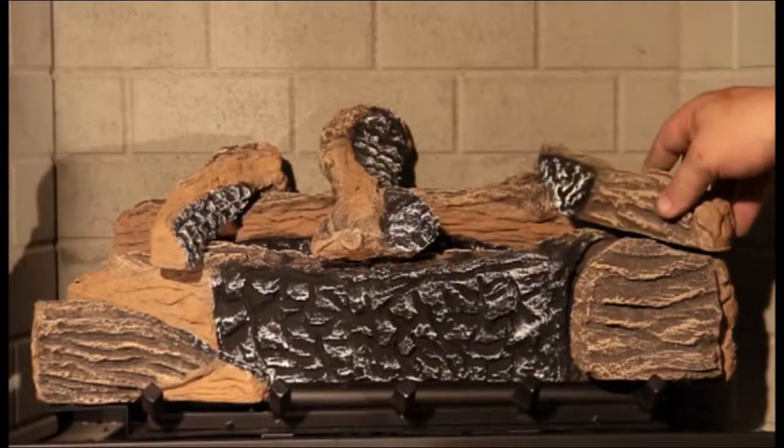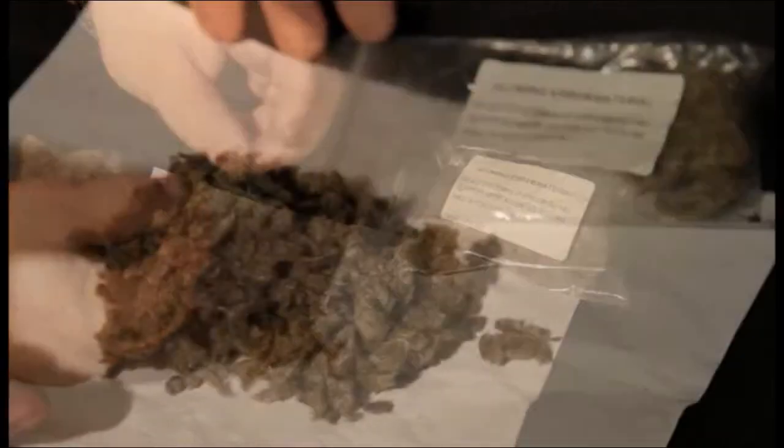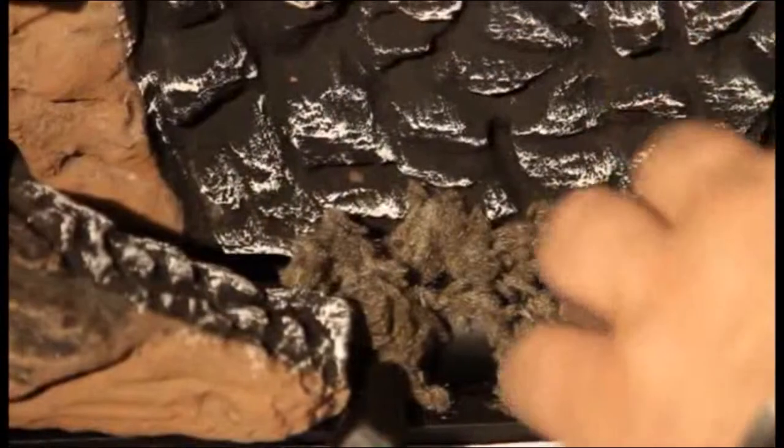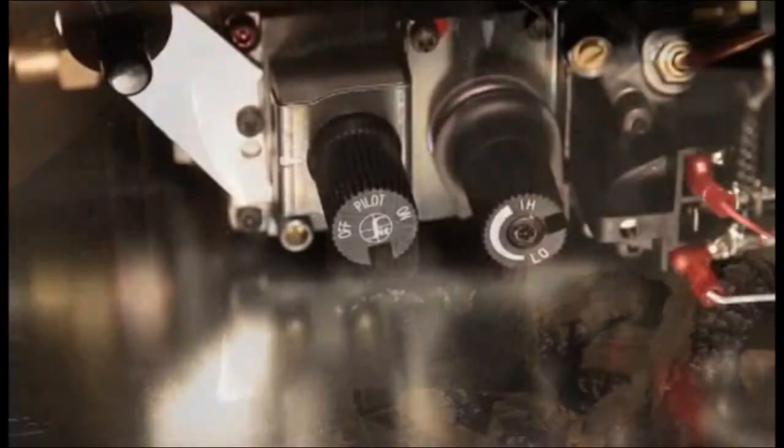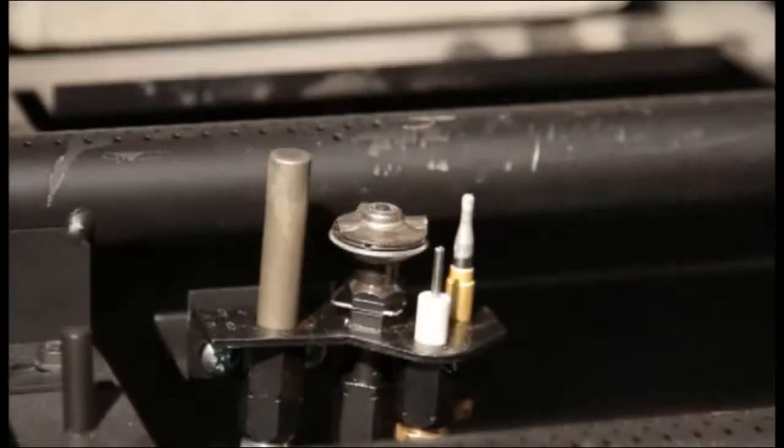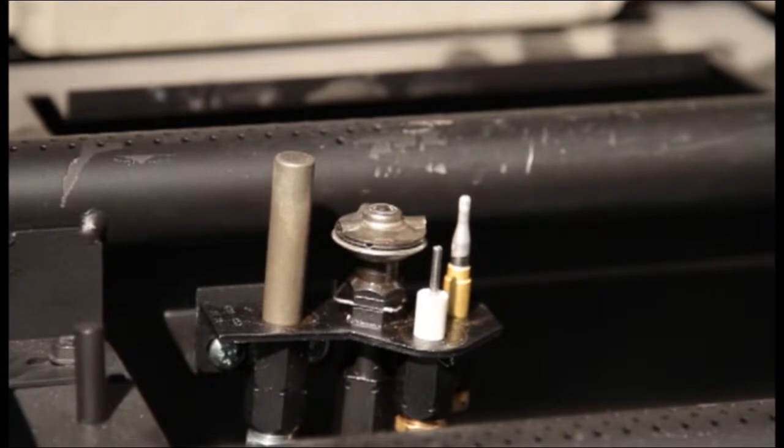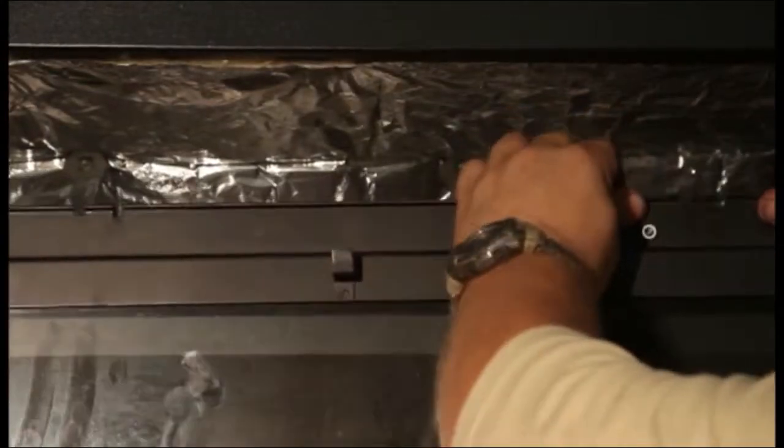Install the logs and embers, which must be no larger than an eraser, according to the installation instructions. Leak check the gas control and any connections you've made before operating the appliance. Close and latch the door, latching the top two latches first.